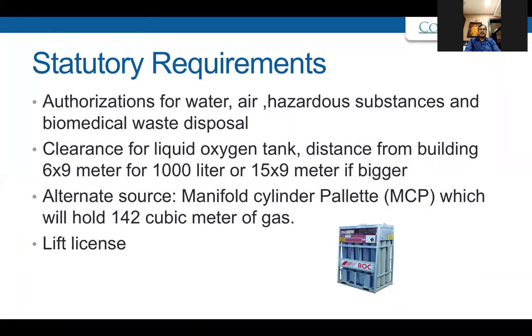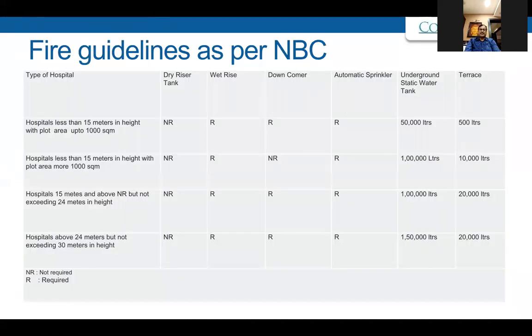It contains approximately 25 cylinders, almost 142 cubic meters of gas, which is a day's requirement, I would say, for a small hospital. But for a bigger hospital, you may require 3 pallets like this per day. The only problem with this pallet is that you have to put it through a crane because it is very heavy. You can imagine 25 cylinders having to be brought inside. Lift license is compulsory in almost all the states which I have visited for NABH accreditation, except one odd state where lift license is not compulsory, and it is a lifetime lift license which is given.